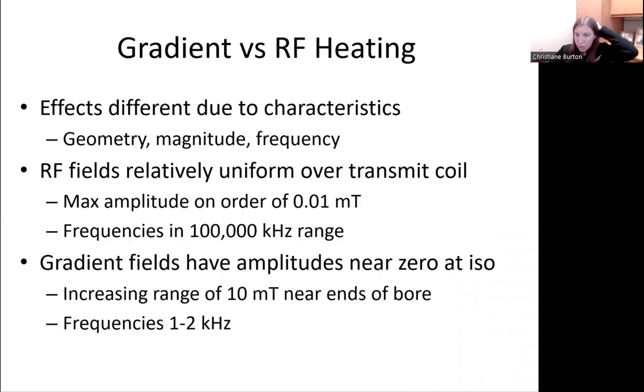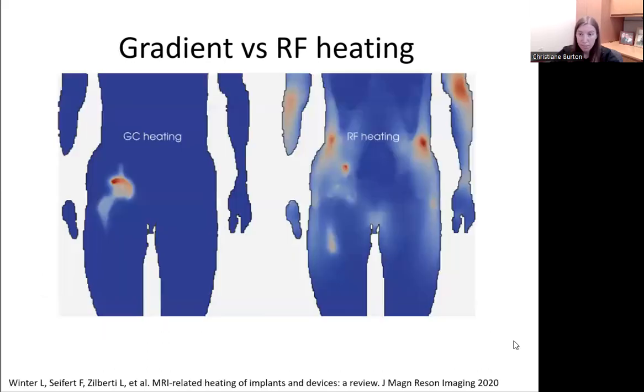So both RF and gradient fields produce tissue heating, but the effects are different because of the geometry, magnitude, and frequency characteristics of each. In typical MRI applications, RF fields are designed to be relatively uniform over the entire volume of the transmit coil. They have maximum amplitudes on the order of 0.01 millitesla and frequencies in the 100,000 kilohertz range. Time-varying gradient fields for spatial encoding are designed to have amplitudes near zero at isocenter, increasing to the range of 10 millitesla near the ends of the scanner bore. Their base frequencies lie in the range of 1 to 2 kilohertz, with harmonics extending to over 10 kilohertz.